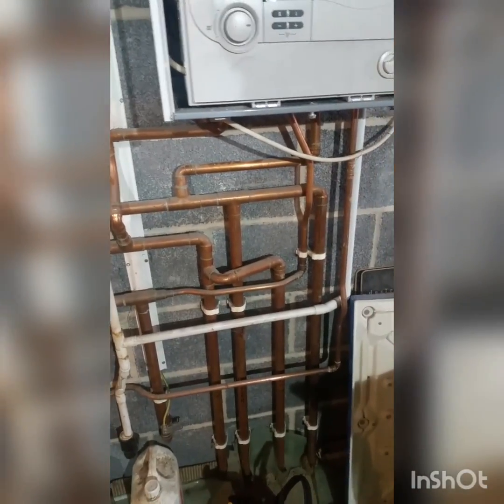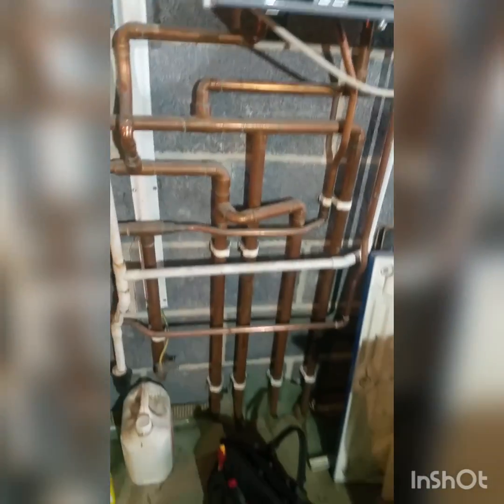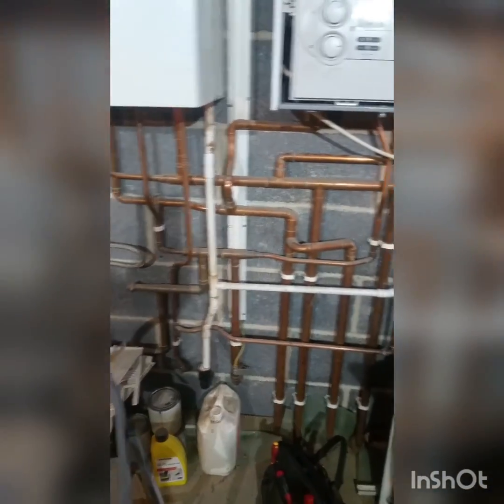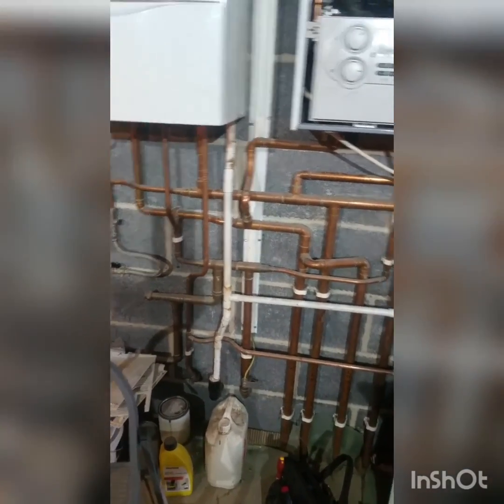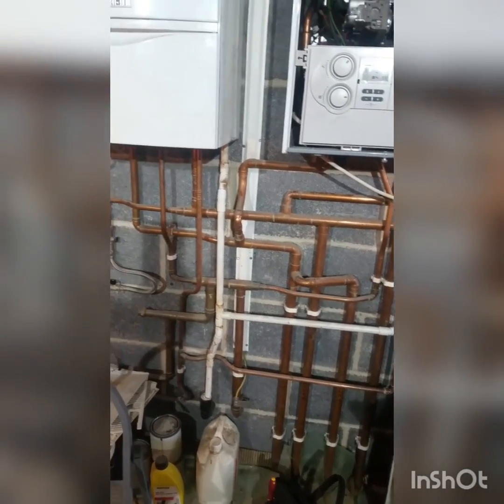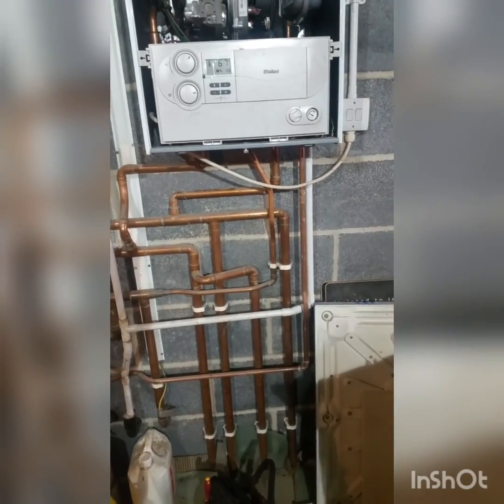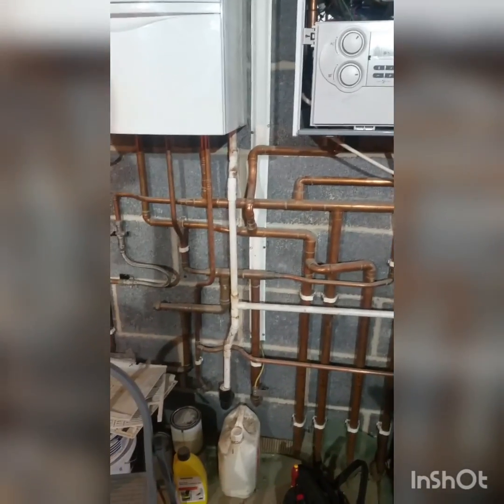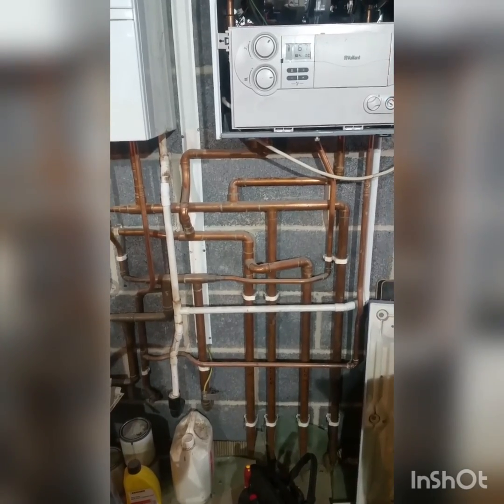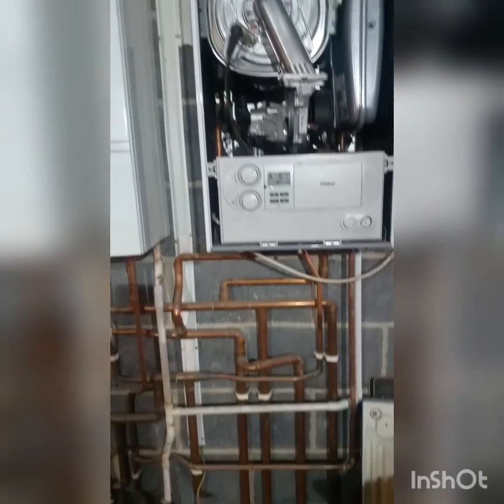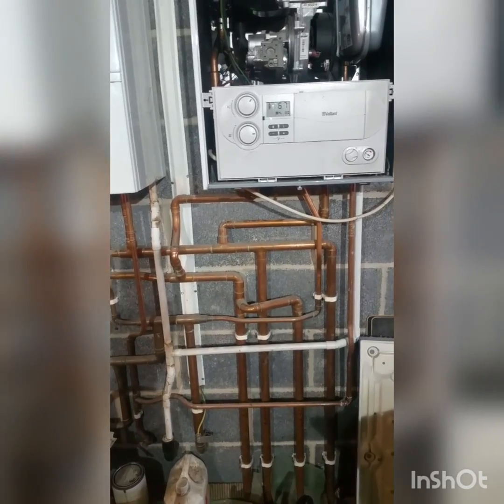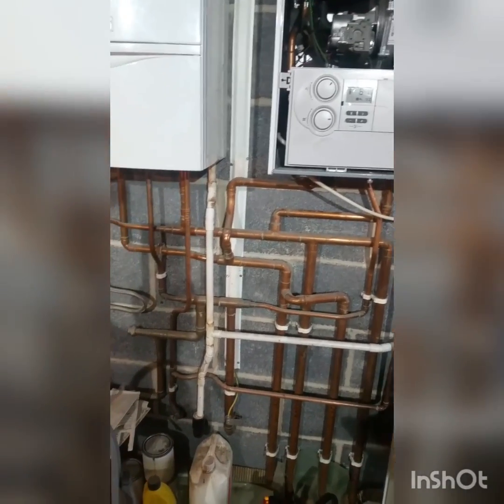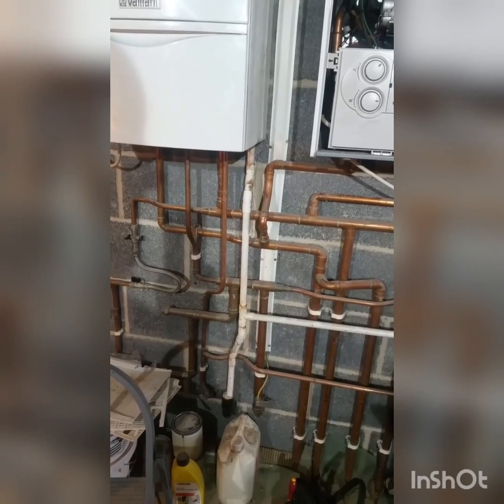But it's a big house, no weather compensation, no real proper controls here. The reason Vaillant have suggested that the heat exchanger would have probably gone is because of the pipework arrangement here. So you've got, it's not even reverse return as far as I can see, but basically it needs to be put into a low loss header or some kind of hydraulic separation, so that the boilers aren't stressed and strained and they can run on their own pumps. So that'll be the next job to do here.